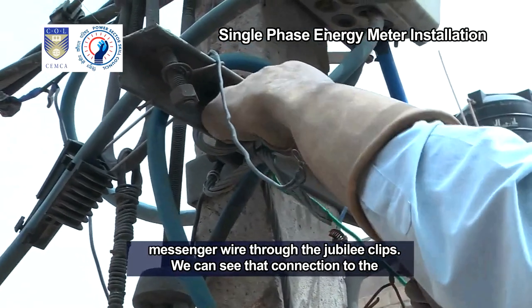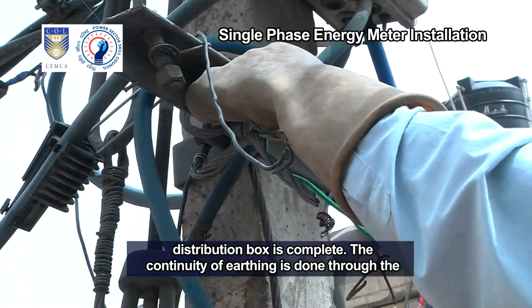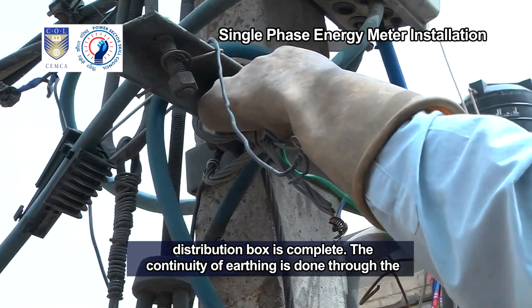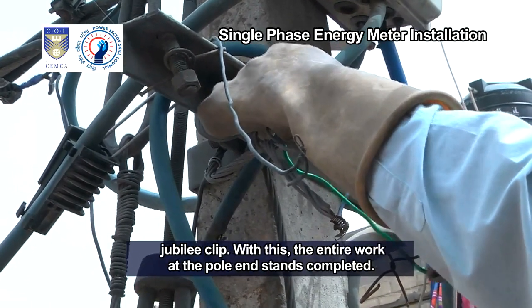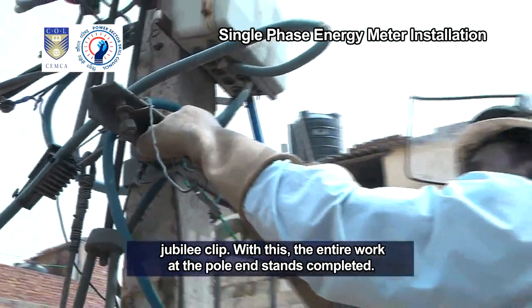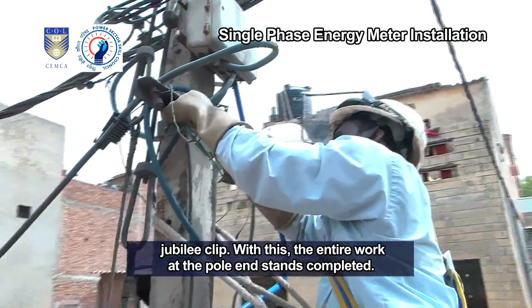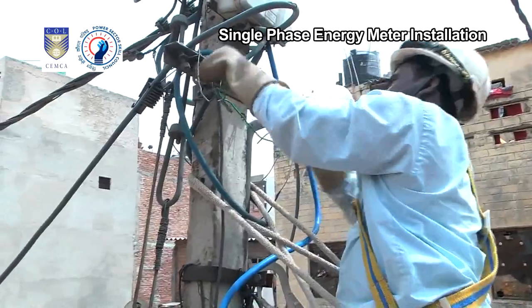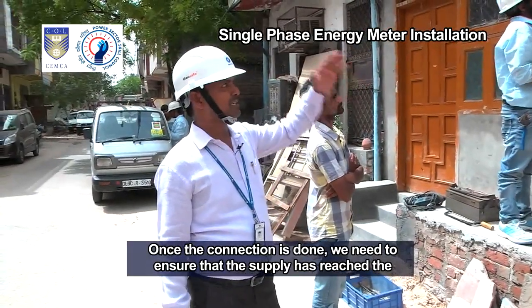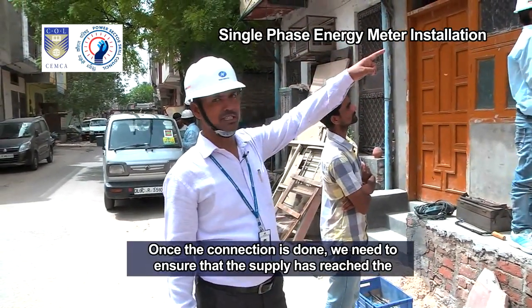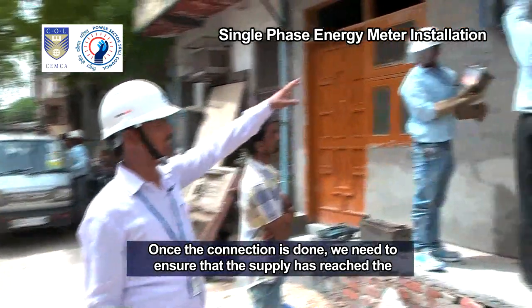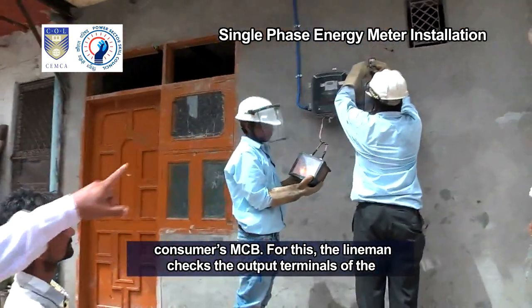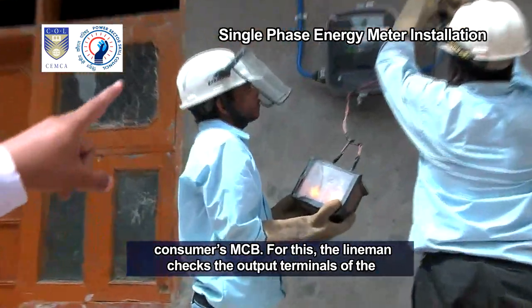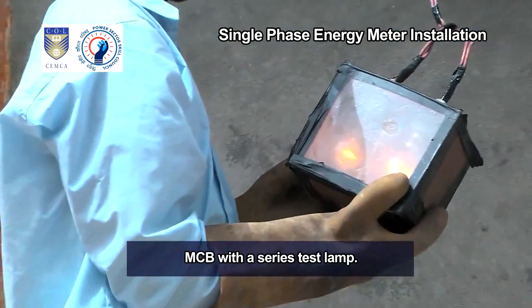We can see that connection to the distribution box is complete. The continuity of earthing is done through the Jubilee clip. With this, the entire work at the pole end stands completed. Once the connection is done, we need to ensure that the supply has reached the consumer's MCB. For this, the lineman checks the output terminals of the MCB with a series test lamp.